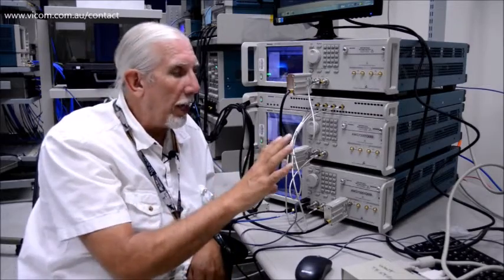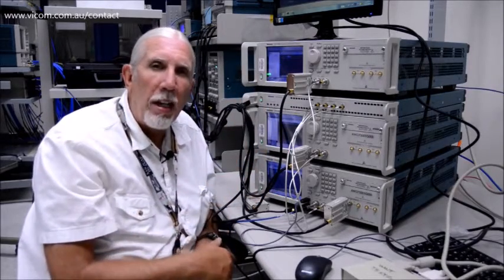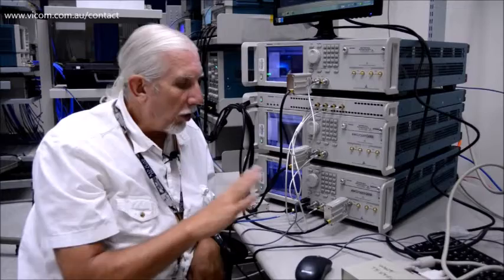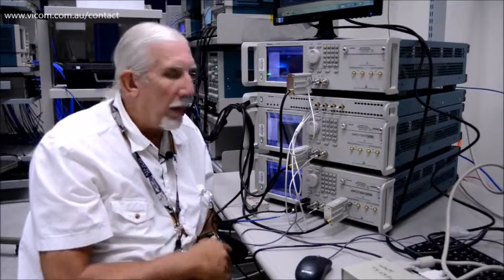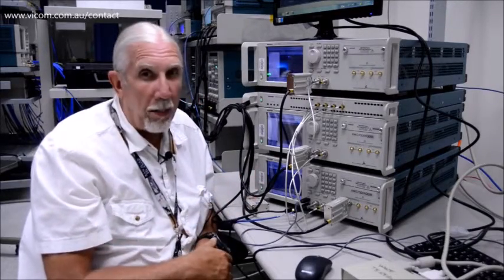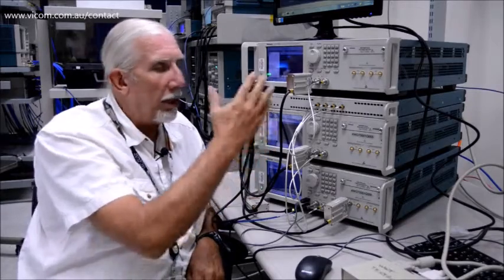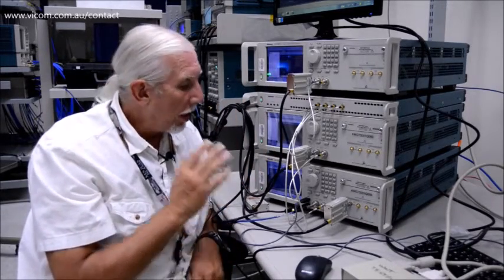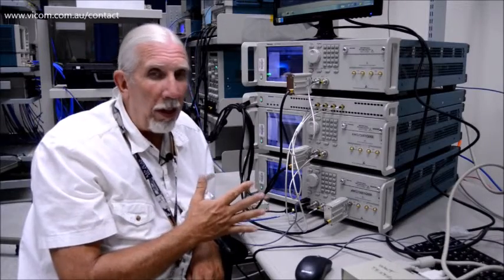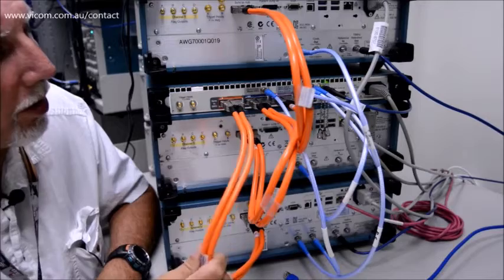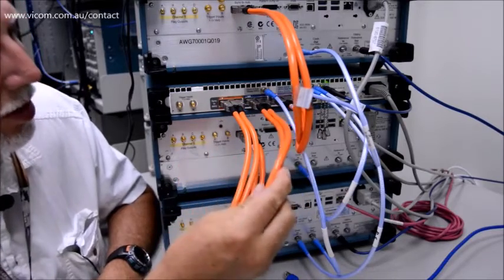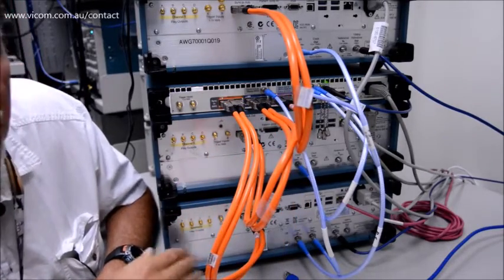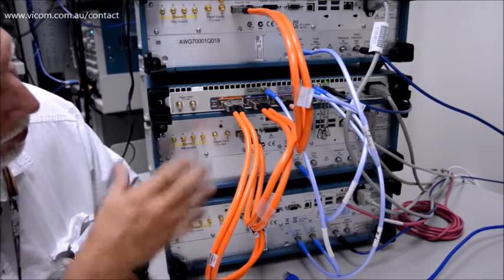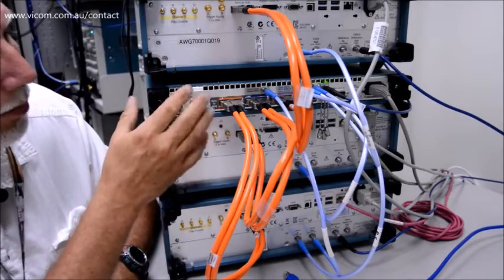So once you've done the calibration, you can remove these cables, and there's really nothing else required except for running your application. So it's very simple, doesn't require an oscilloscope in order to do the calibration, doesn't require any other external devices. From the rear of the instrument, you can see that we have the connections required here from each AWG to the sync hub here.